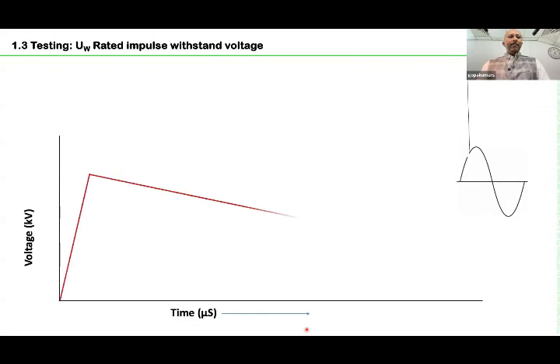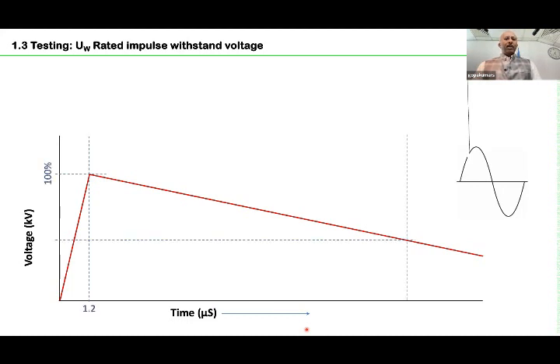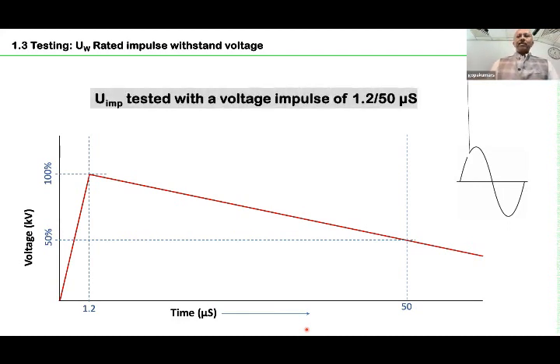Finally, every device which is in compliance with the standard, after manufacturing or design, has a type test. The device has to be tested with an impulse voltage. Impulse voltage means a high voltage for a short duration. The waveform is 1.2 to 50 microseconds. So every equipment is supposed to be tested with this kind of impulse voltage.